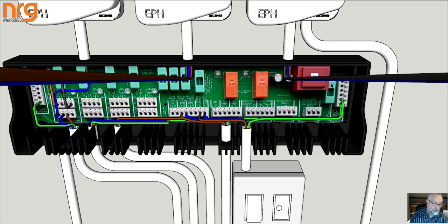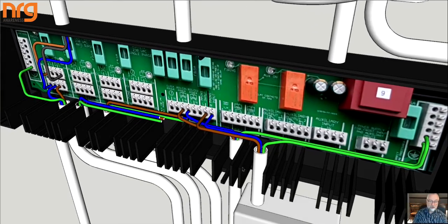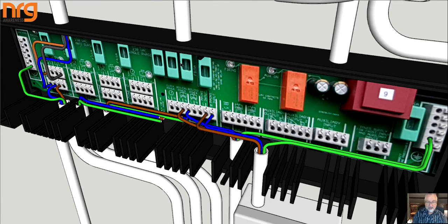There's a completely separate 3-amp fuse over here, and that looks after a power supply to these terminals here. If one of those goes out and feeds, say, through maybe a solid fuel back boiler stat or something, and comes back in to the auxiliary input, if power ever arrives at the input of those stats, then very simply the auxiliary relays will change contact, and you can do whatever you want with the voltage-free contact switching. So, again, with the OpenTherm boiler, we need a live and neutral, so we're taking it from here. Boiler 1, live and neutral, brown wire, blue wire for neutral, and it goes off over to the boiler.